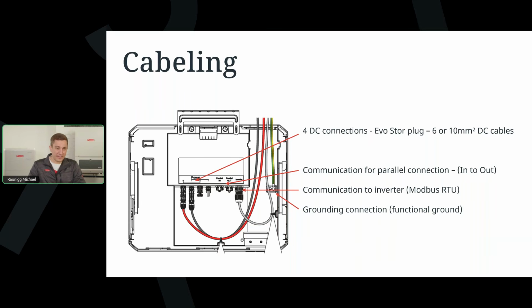On the connection area itself, you will then get an input and an output always. So always plus and minus input, plus and minus output. And as you can see, the second output is then being used for the parallel connection. So whenever you go into a second or third tower, you can use this output DC connection to just cable your cable from the first battery to the second to the third and so on. So no hassle within any DC combiner boxes or whatever. You're just placing your DC cables on the second output, and then you go on to the second system.